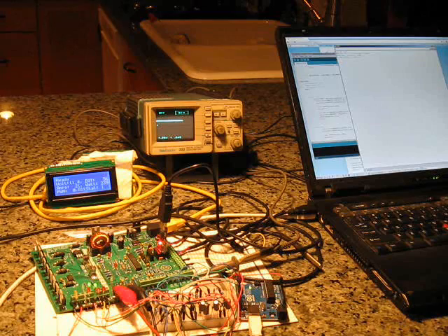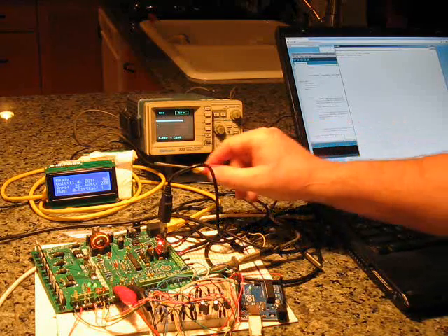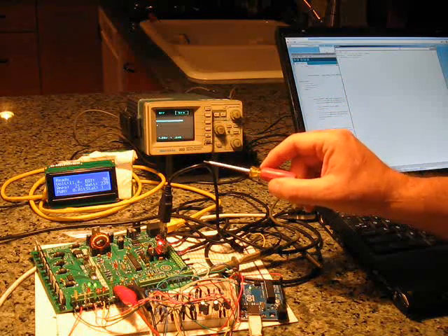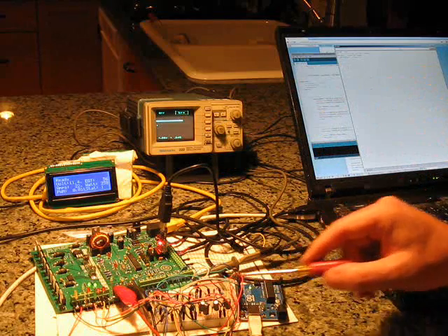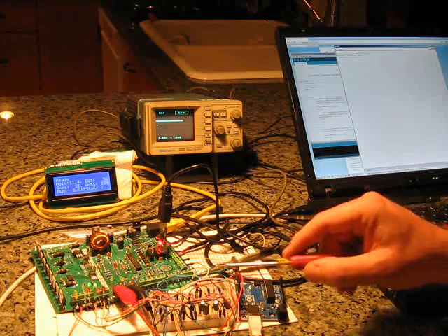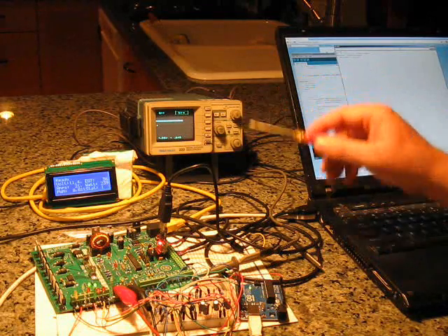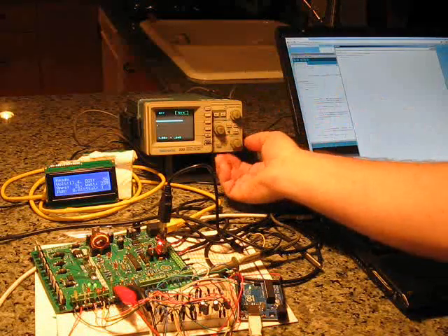What we're going to show here is a simulated run of the Smart Engine Controller and Alternator Regulator. We've connected it up and powered it up. We have the LCD display screen, this service serial port attached to the service connector, our emulator, our simulated generator and DC battery. I've also connected an oscilloscope up to the simulated stator line so we can monitor the RPMs that are produced.